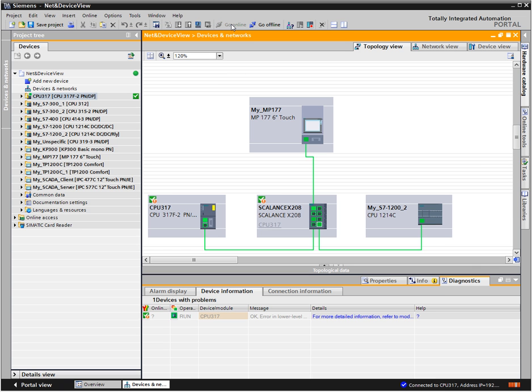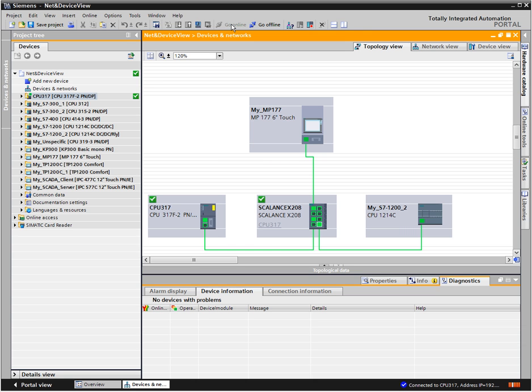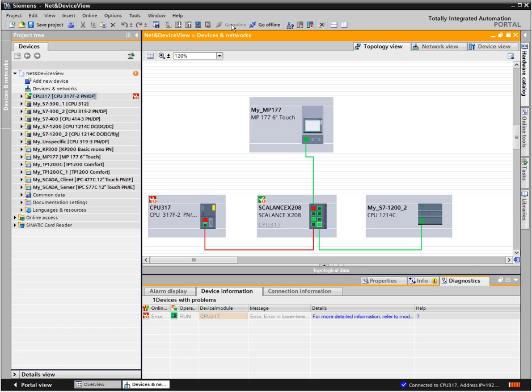If the offline configuration corresponds with the real physical interconnection, then the line is displayed in light green. If a communication disruption occurs, the respective connection and the respective ports are highlighted in red, after automatically updating the status. Additionally, the diagnostic status is displayed in the tabular range of the topology view.